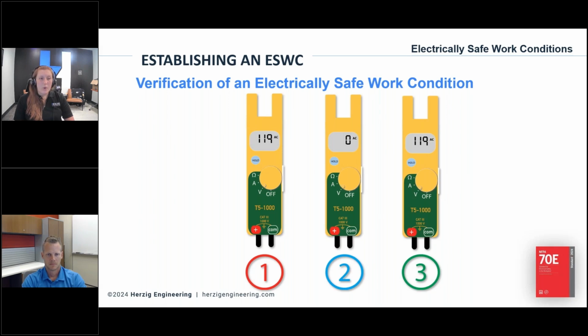Okay, so in this example, the triple check is a known outlet, like a 120 volt outlet. We've got 119 is what we're reading, 118, 121, somewhere in that nominal range. That's an acceptable, expected reading to get. And then you go to where you're going to be working, where you're actually going to stick your hands in, and get 0 for everything. Live, phase to phase, phase to ground, everything. And then go back to that same known source and you should get the same reading.